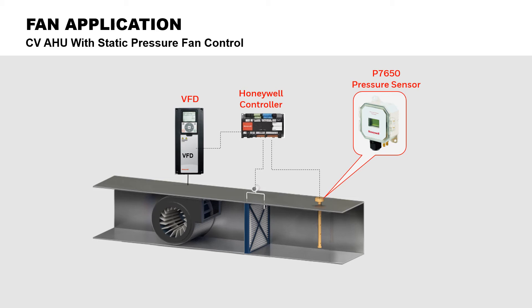The fan in this example is constant volume. The VFD modulates the fan based on a sensor measuring the static pressure downstream from the filter. As the filter loads up, the fan will ramp up to maintain constant airflow.